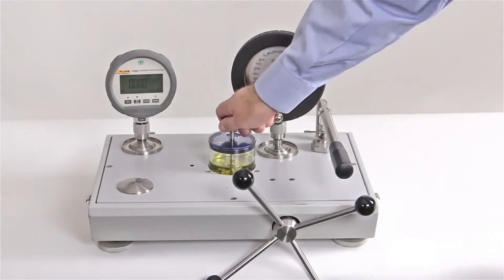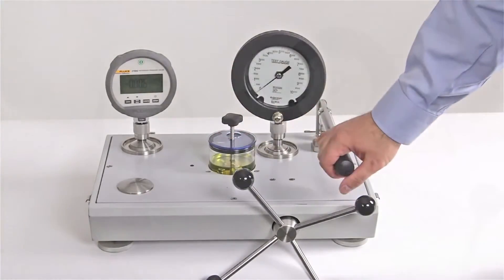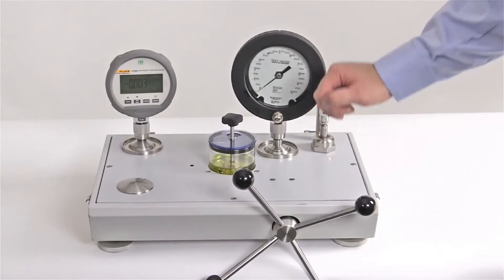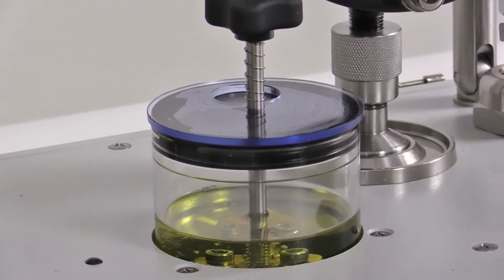With the reservoir valve open, the built-in priming pump can then be used to prime the system. The priming pump includes a check valve system so that the fluid is drawn from the reservoir and pushed through the system. The air in the system is then pushed out through the reservoir.